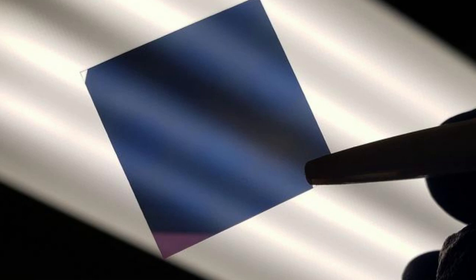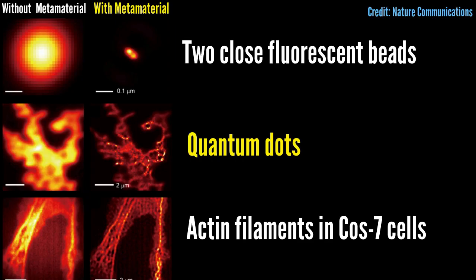As light passes through, its wavelengths shorten and scatter to generate a series of random high-resolution speckled patterns. When a sample is mounted on the slide, it gets illuminated in different ways by this series of speckled light patterns. This creates a series of low-resolution images which are all captured and then pieced together by a reconstruction algorithm to produce a high-resolution image.